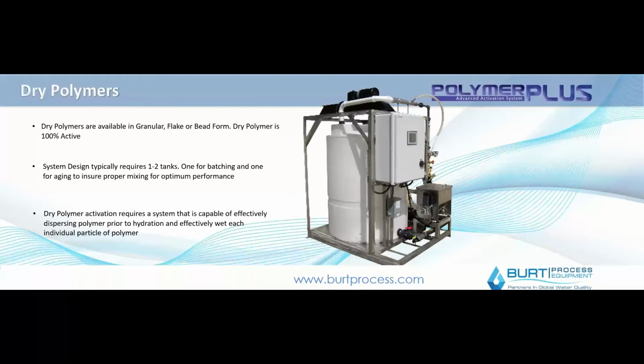Thus far, we've really focused on liquid feed systems, but dry polymer is also used, and some people do have a preference for it. Dry polymer operates a little bit differently in that you're not trying to necessarily activate it in quite the same way or strip off the oil, but now you're basically going through a dilution-based system, which then goes into either a tank or some kind of a blending and aging chamber prior to use. There are pros and cons to both of these. Obviously, liquid polymer has a shelf life associated with it, so you do have chemical drums that you need to maintain. Talking about solids, you can hold a lot more solid polymer for a lot longer, but you do have to be concerned about humidity impacting that. If you do have a high humidity environment, solid polymer can begin to interact with itself before you even get a chance to utilize it within your actual system.